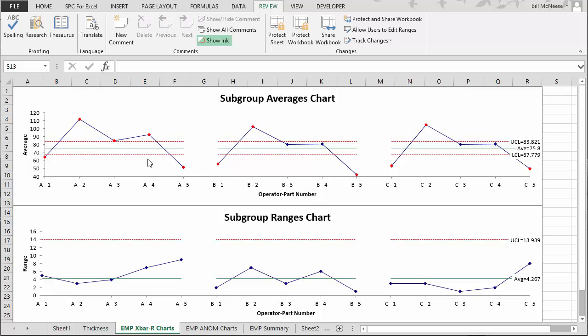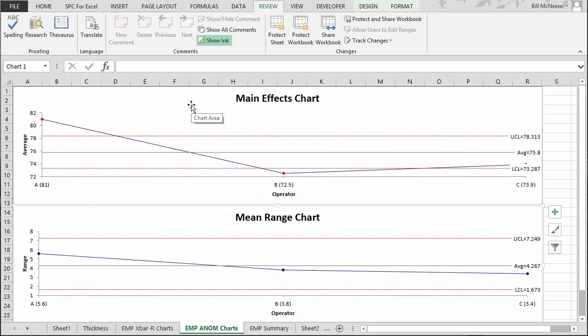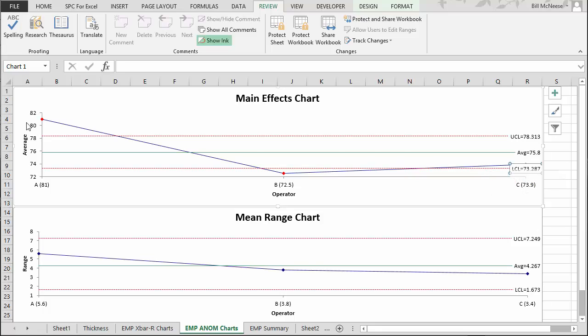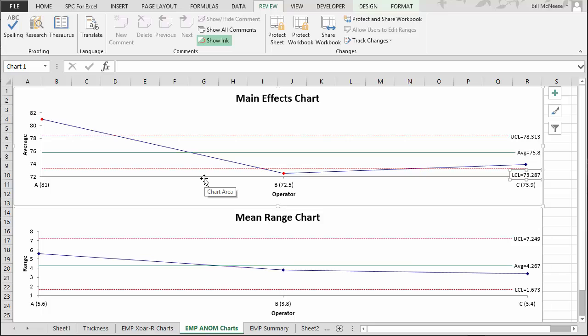We can confirm suspicions about Operator A having different averages — that is, that bias exists — by using the main effects chart. We calculate an average for each operator: Operator A's average is 81, Operator B is 72.5, and Operator C is 73.9. Control limits are calculated using scaling factors. Operator A is above the upper control limit and Operator B is below the lower control limit. B and C are very close, while Operator A has a clearly different average, indicating bias in the test method that will increase variation attributable to the measurement system.